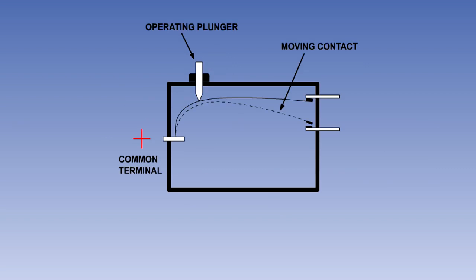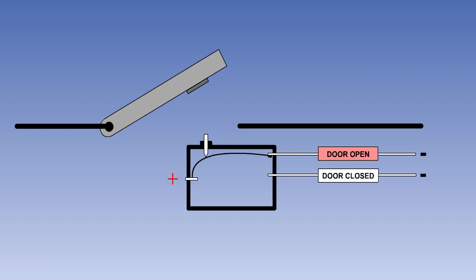In the typical example shown here, the moving contact is on a spring arm, which will hold it against the upper contact. When the component being monitored reaches the required position, the striker plate will push down on the plunger, causing the moving contact to move down and connect with the lower contact.